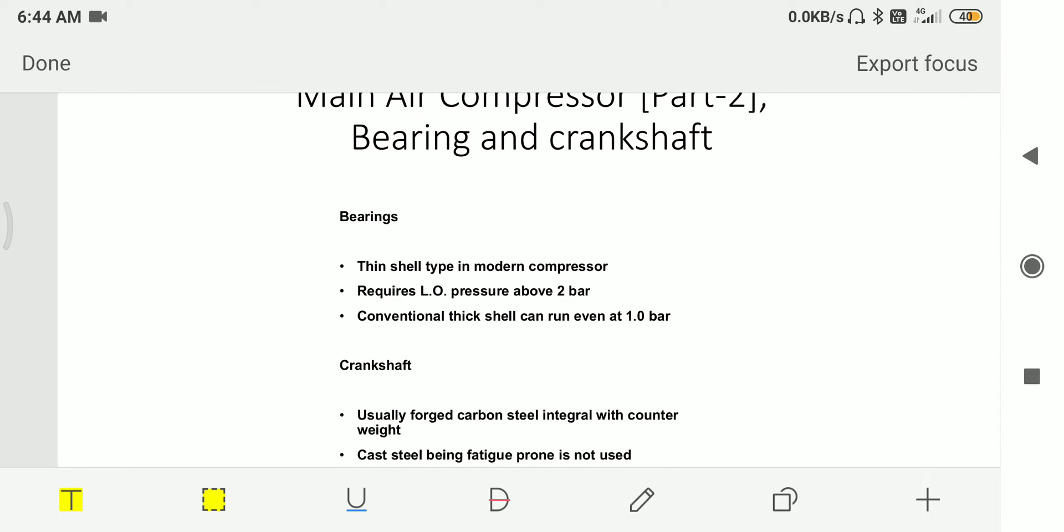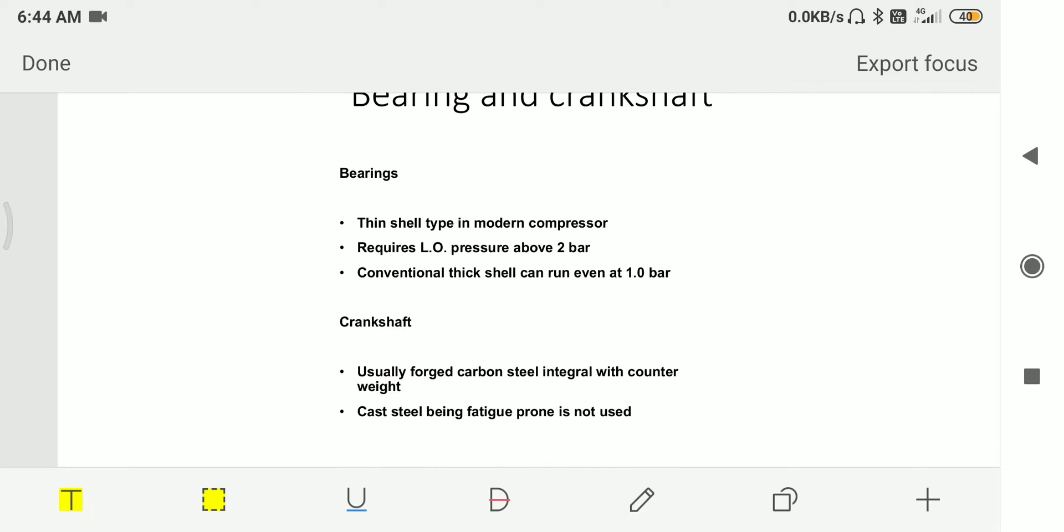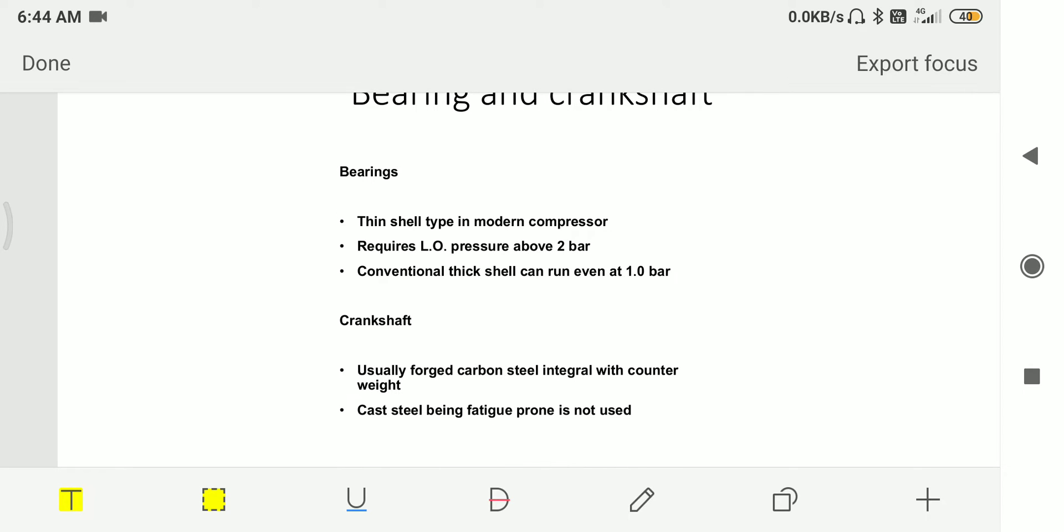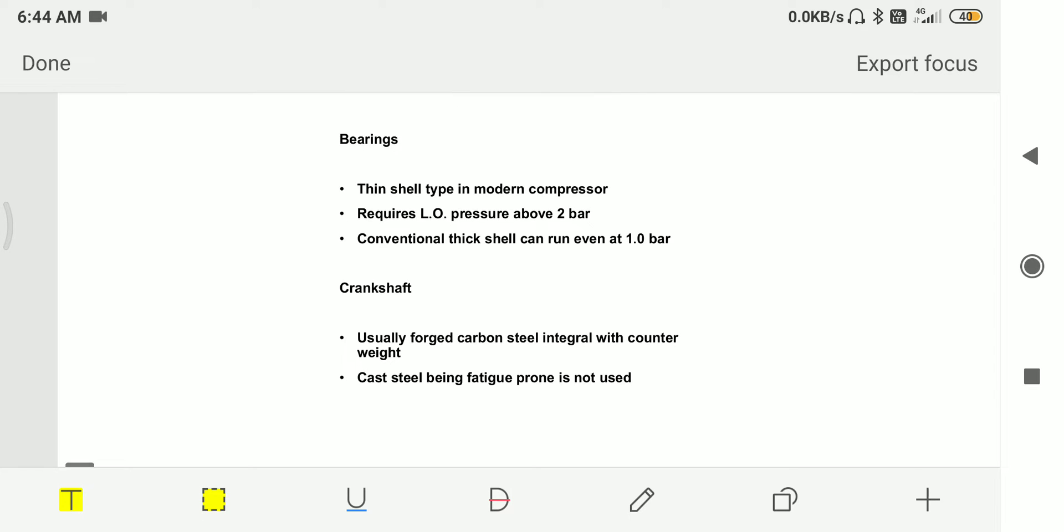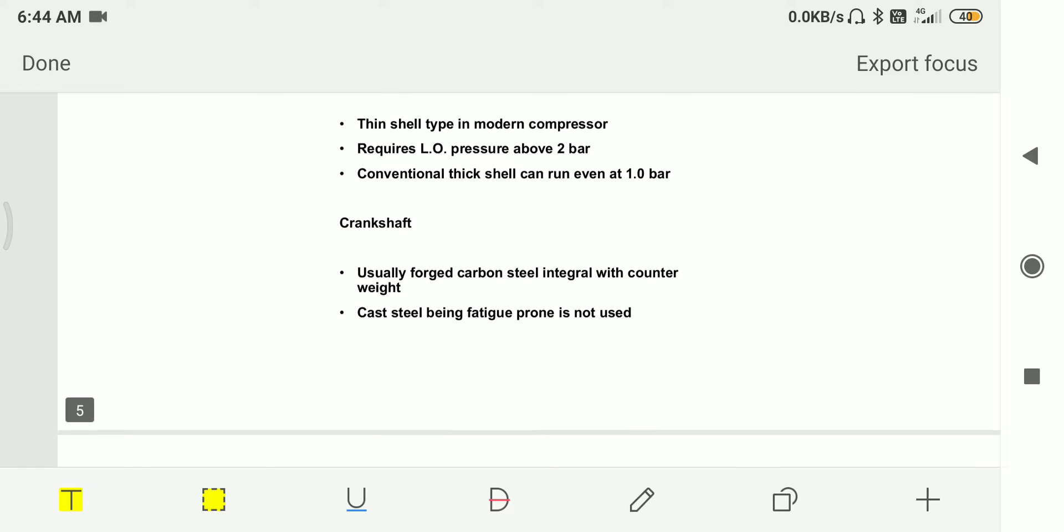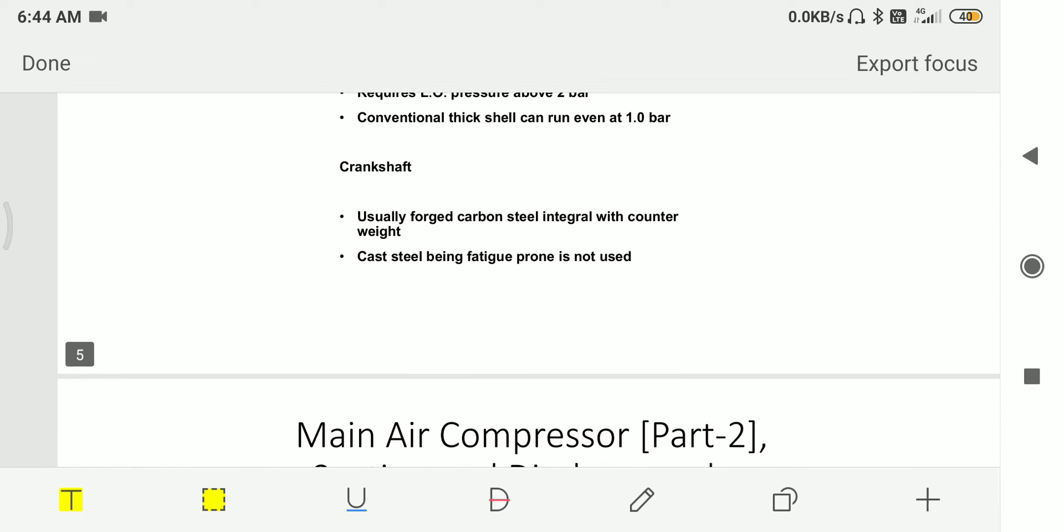Then we have bearing and crankshaft. Bearings are mostly thin shell type in modern compressors, and the lube oil pressure required is 2 bar. For thick shell bearings, the lube oil pressure required is 1 bar only. Then we have crankshaft, usually forged from forged carbon steel, integrated with counterweights.